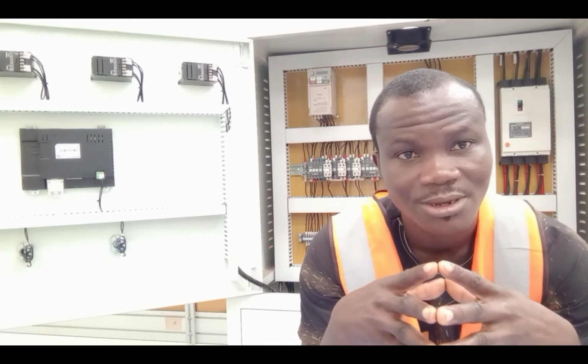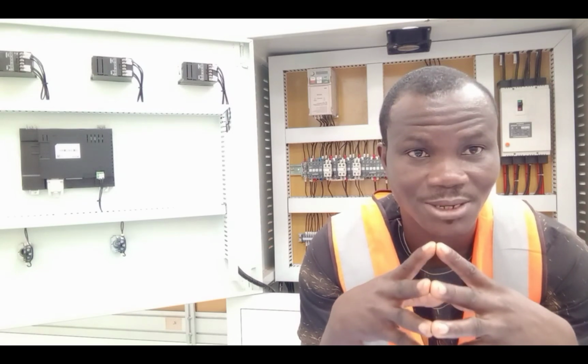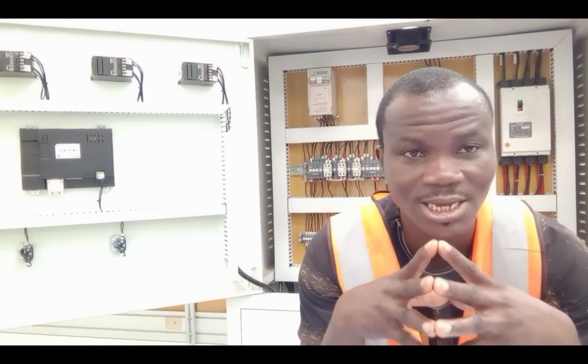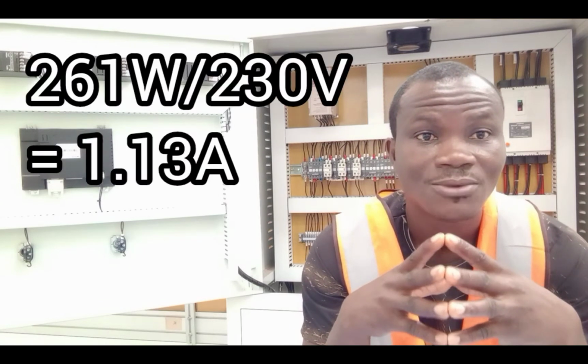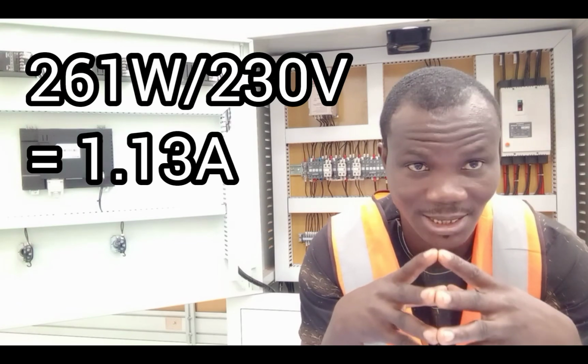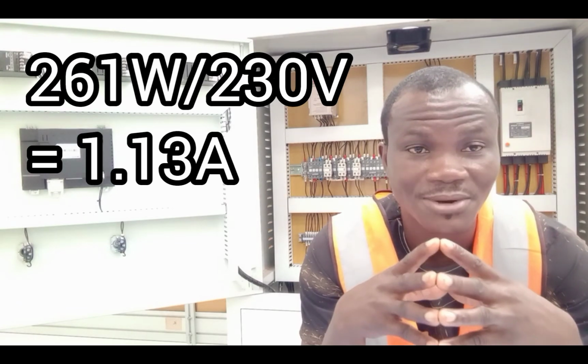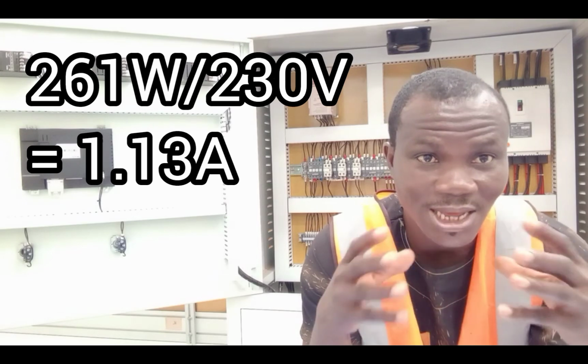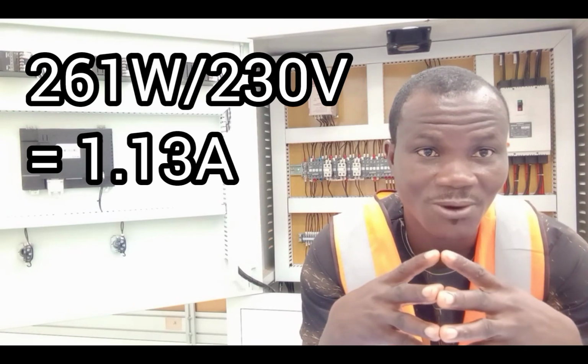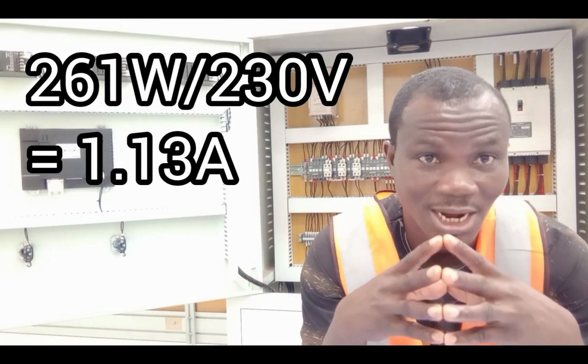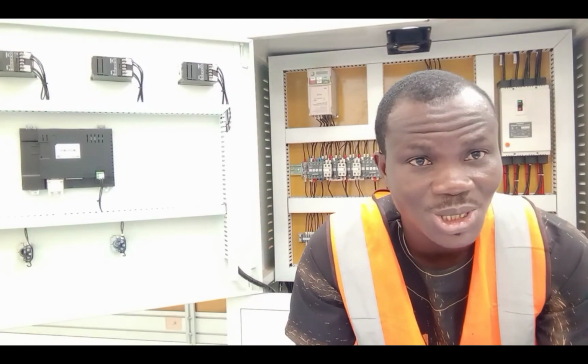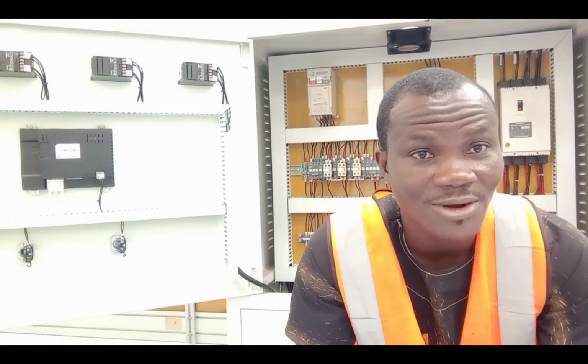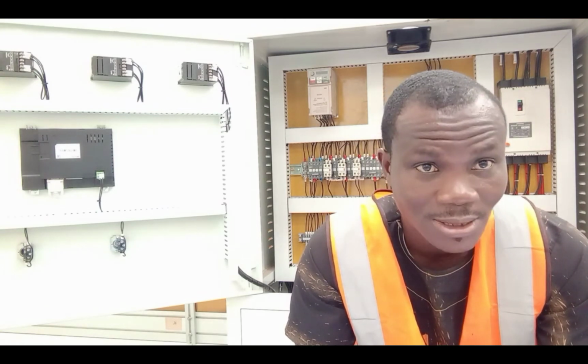So knowing the power and the voltage, to find the current, you divide the power rating by the voltage. In this case, we are dividing 261 watts by 230 volts, and that gives us a current of 1.13 amps.